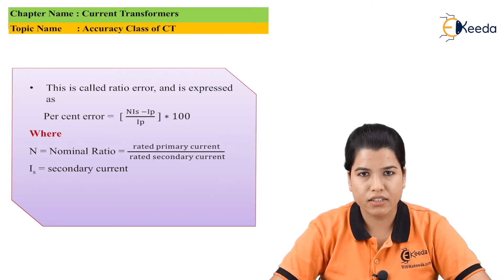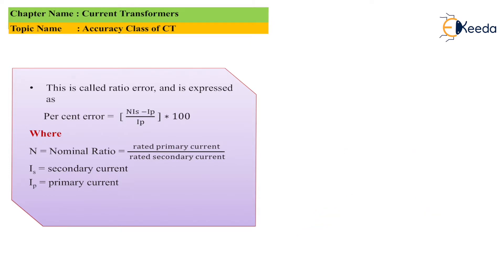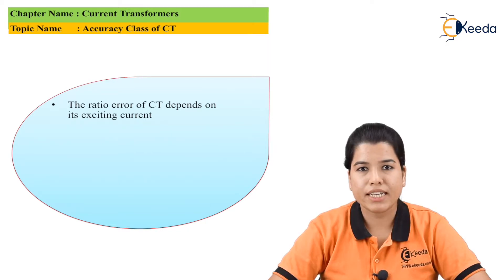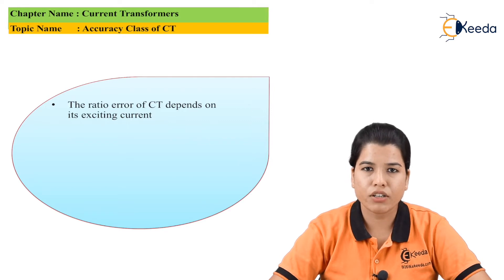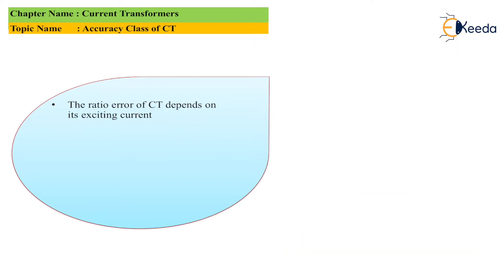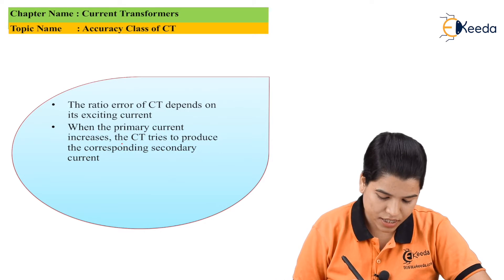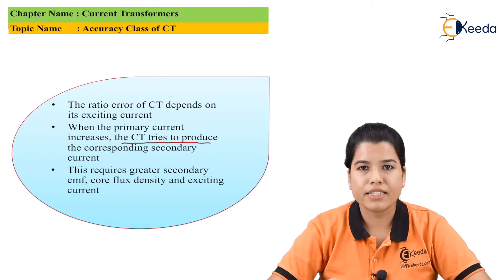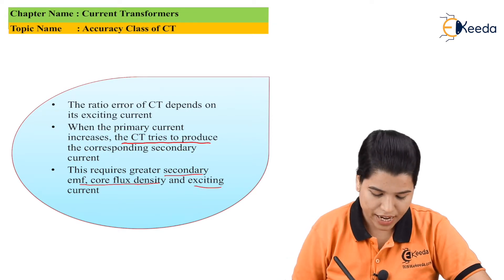Is is the value of secondary current and Ip is the value of primary current. The ratio error of the CT depends upon its exciting current. The exciting current is the phasor addition of the working component current and the magnetizing current. When the primary current increases, the CT will try to produce the corresponding secondary current, which requires greater secondary EMF, then core flux density and exciting current.